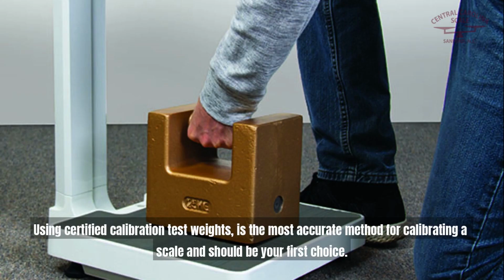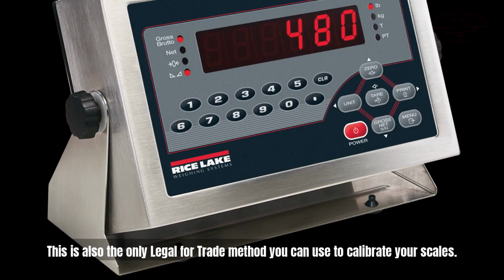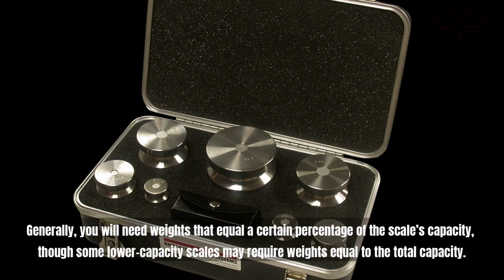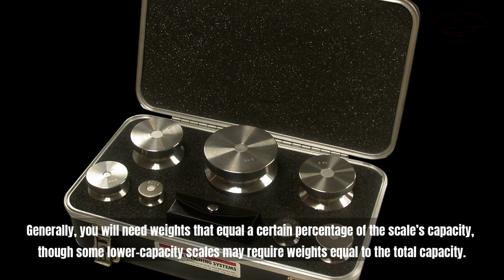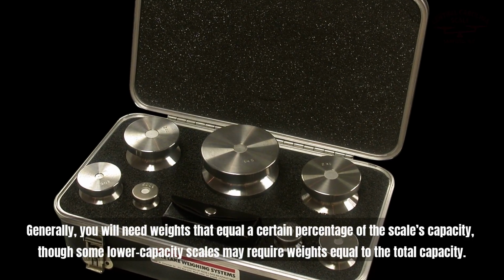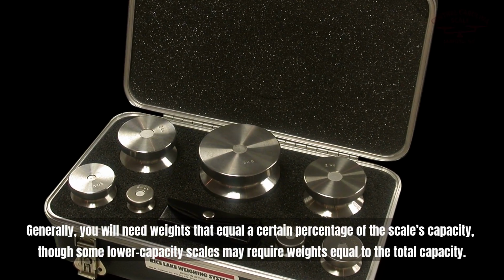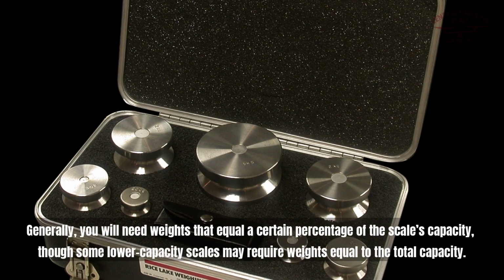Using certified calibration test weights is the most accurate method for calibrating a scale and should be your first choice. This is also the only legal for trade method you can use to calibrate your scales. Generally, you will need weights that equal a certain percentage of the scale's capacity, though some lower capacity scales may require weights equal to the total capacity.